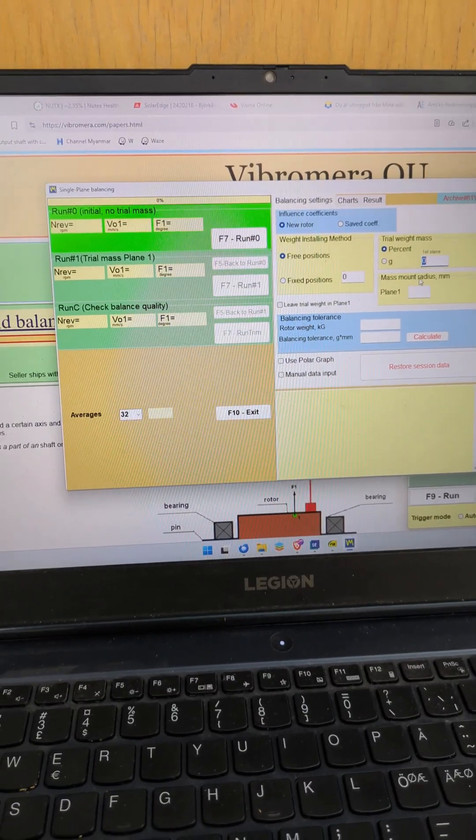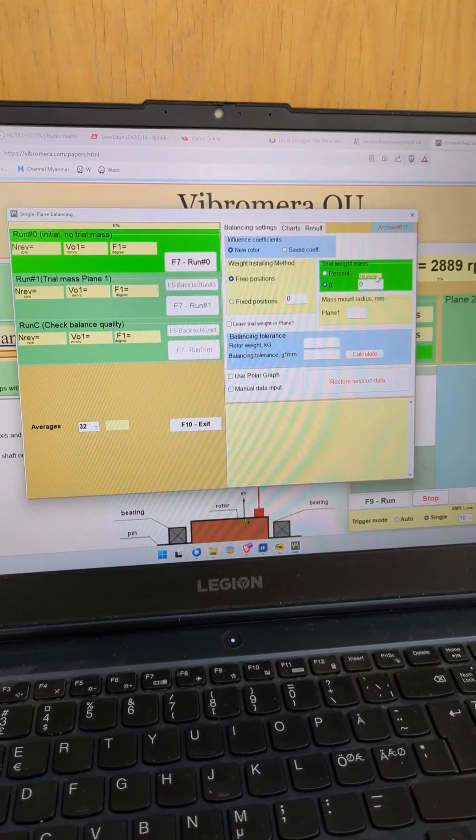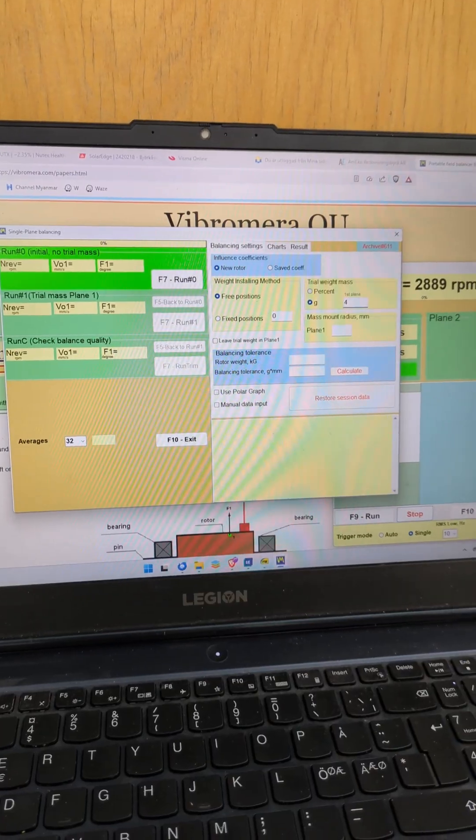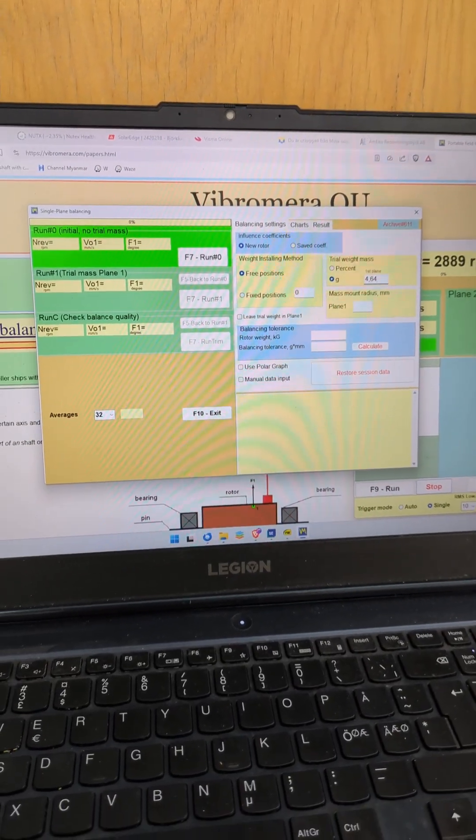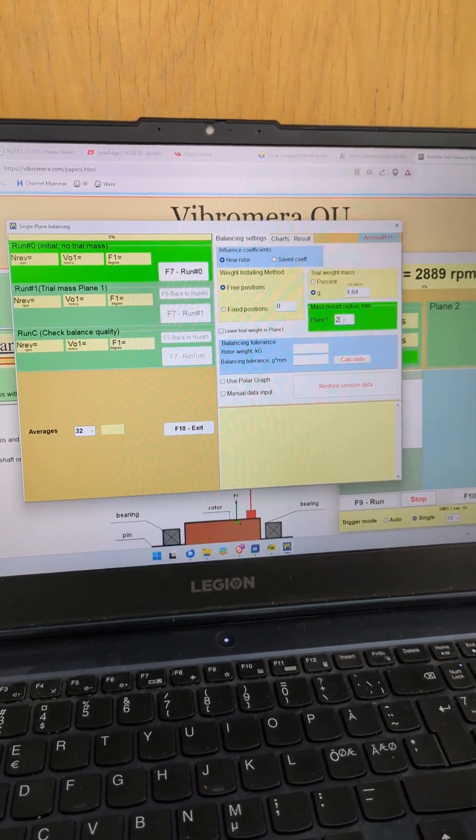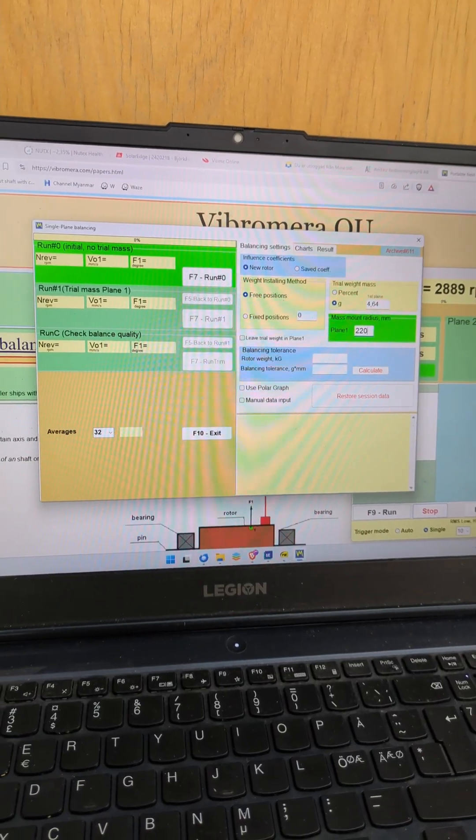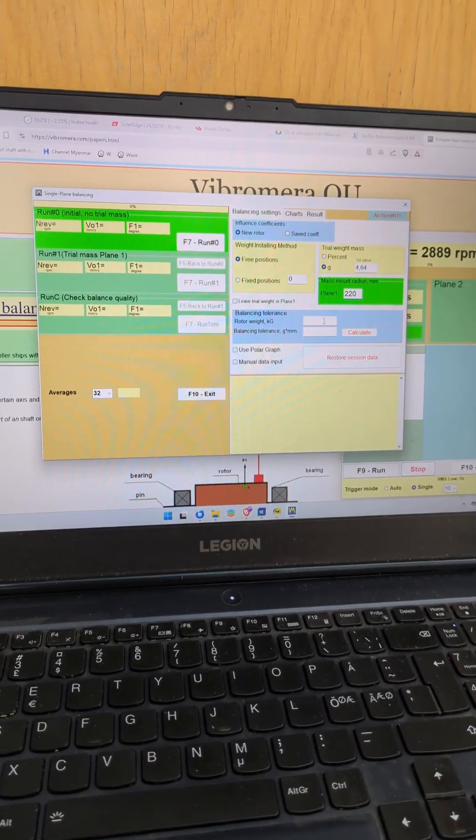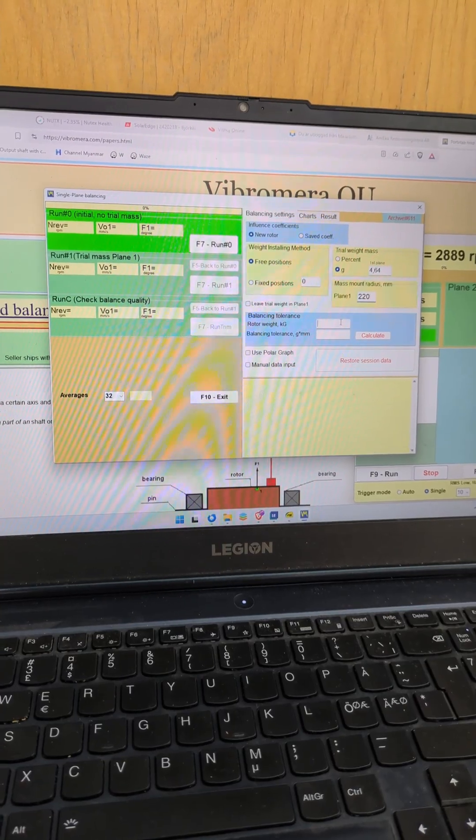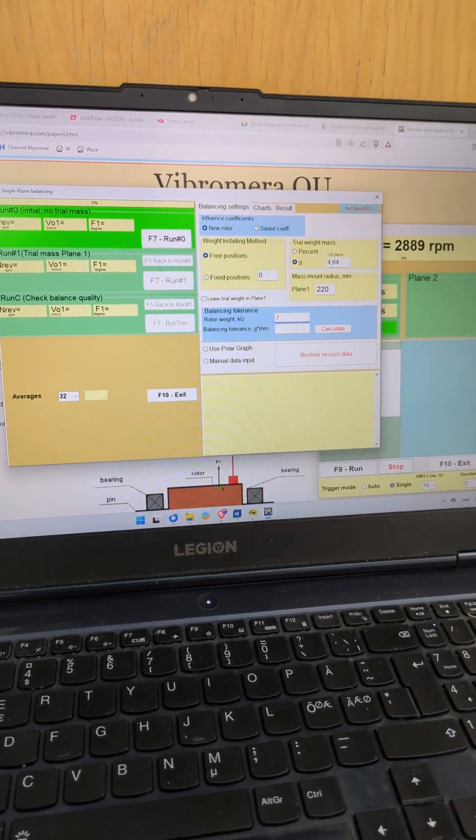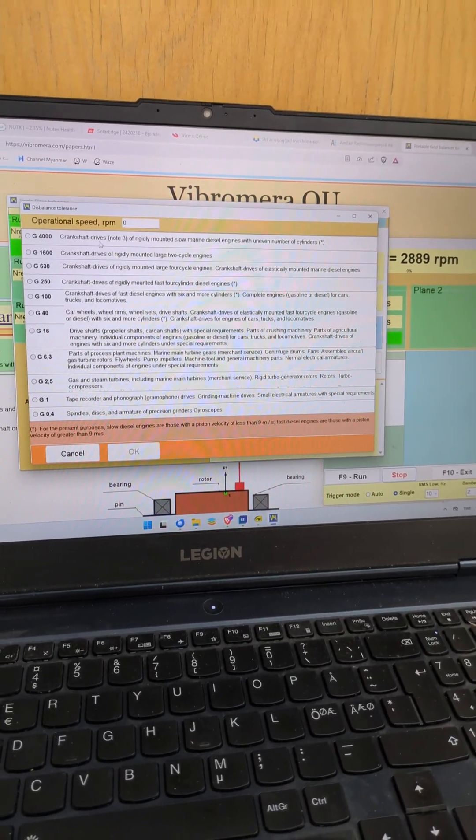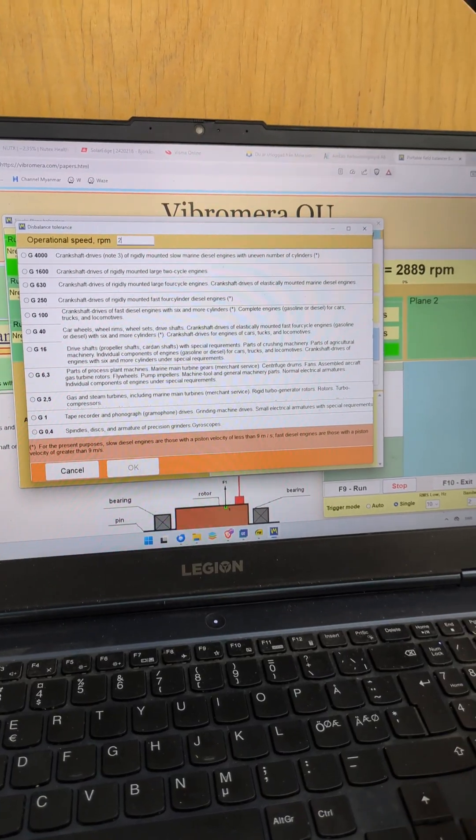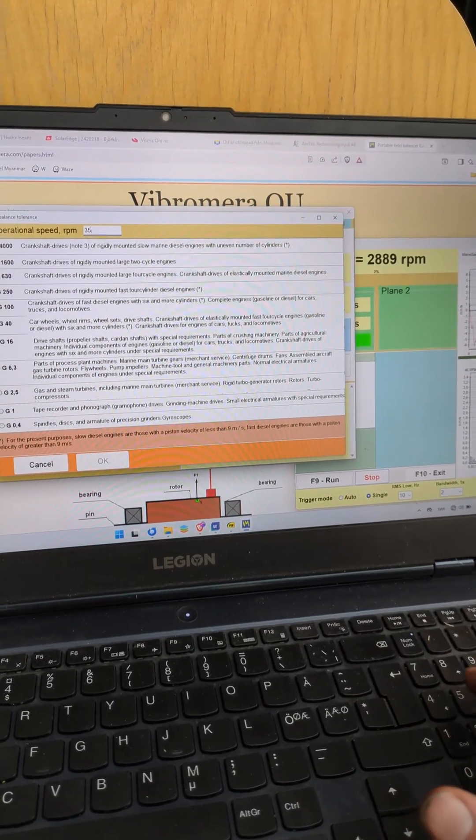Now we select the trial weight in grams. We measured 4.64 and its position on the radius 220 on the fan wheel. The fan wheel weight is 7 kilo.